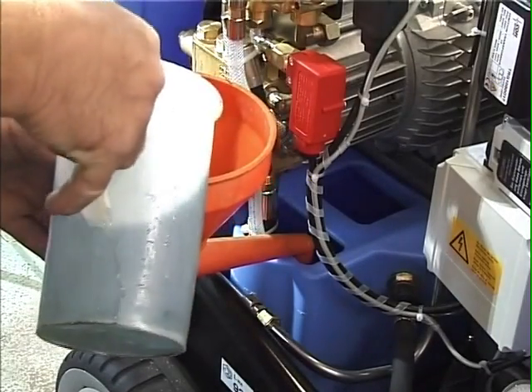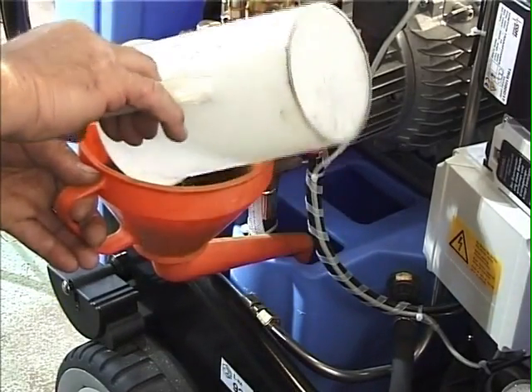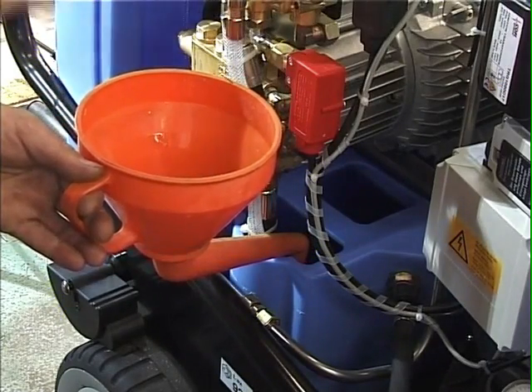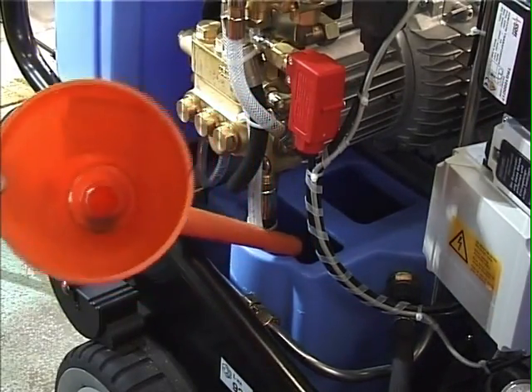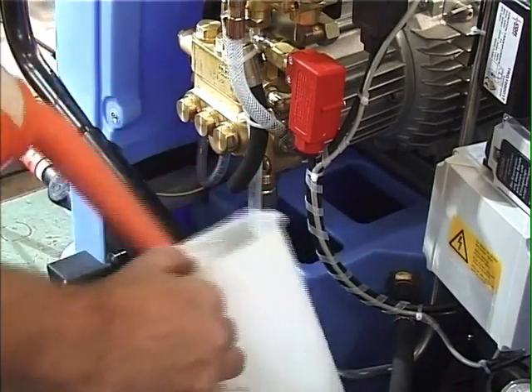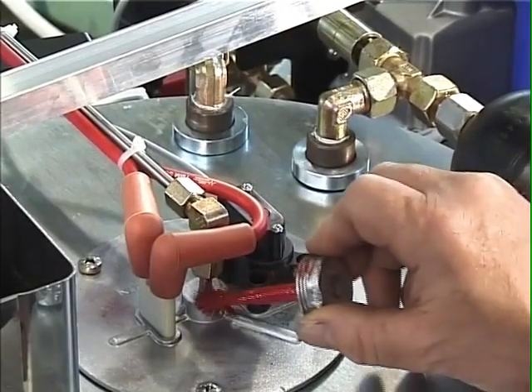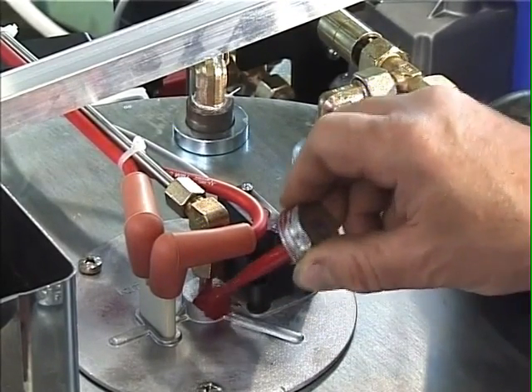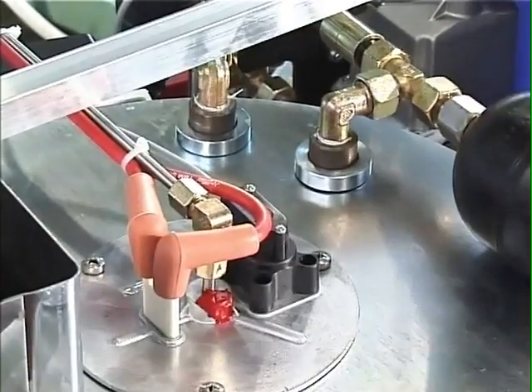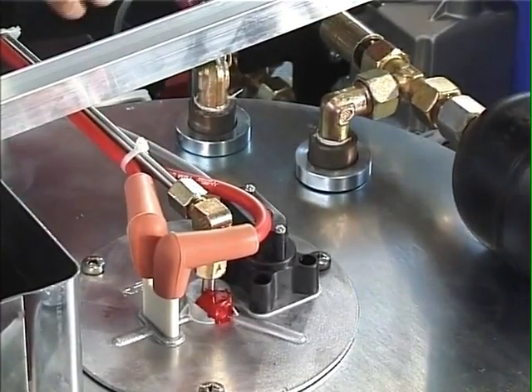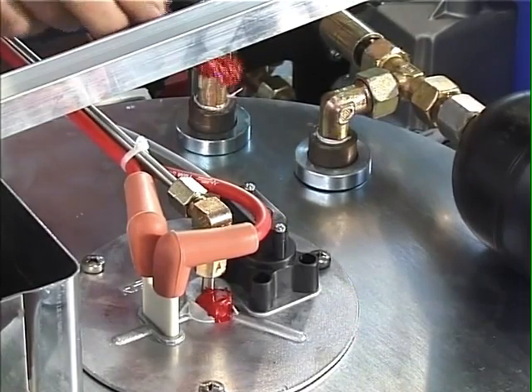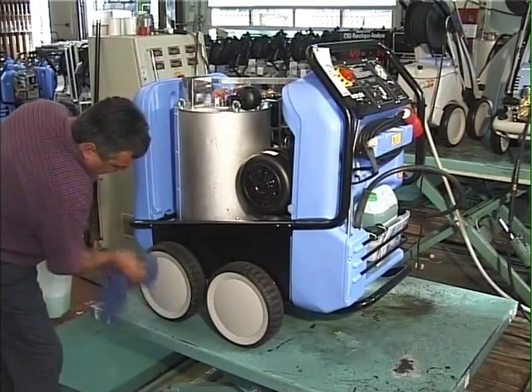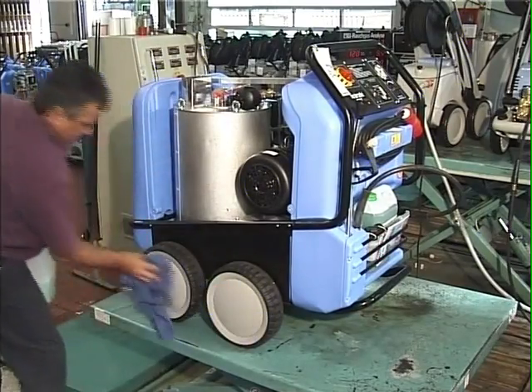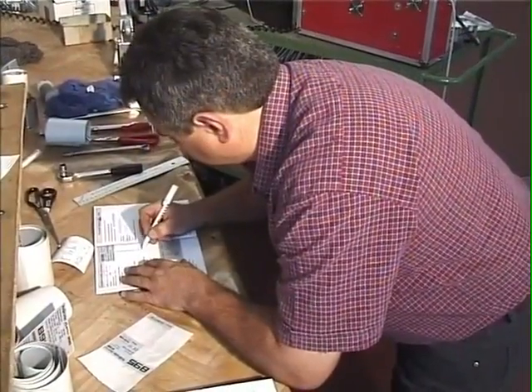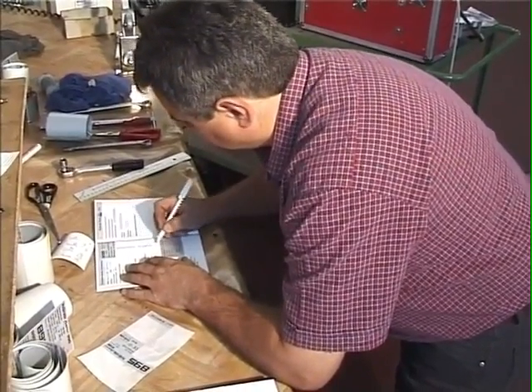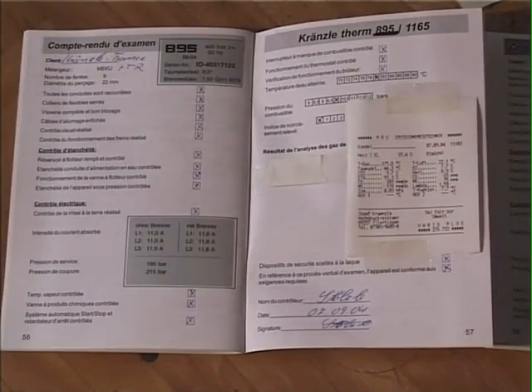The antifreeze is filled into the machine and placed into the entire circuit. The red paint seals certain setting screws to guard against incorrect settings. If the machine satisfies all requirements, the measured results and the test protocol are attached to the respective operating instructions or placed into the operating manual.